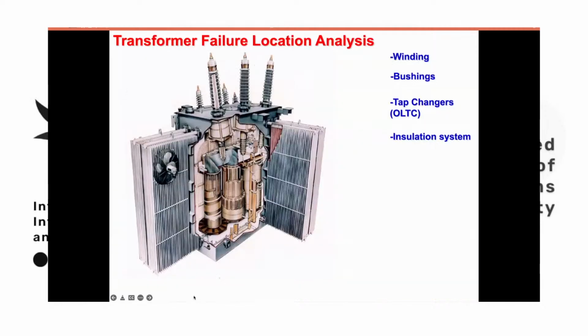The power transformer itself is a very complex piece of equipment, which has many components, including the active winding, low voltage and high voltage winding, the bushing, and the tap changer, which is the only mechanical part in the transformer, changing the turns ratio between low voltage and high voltage. There is also the insulation system, which has paper to keep the mechanical integrity of the transformer, and oil.